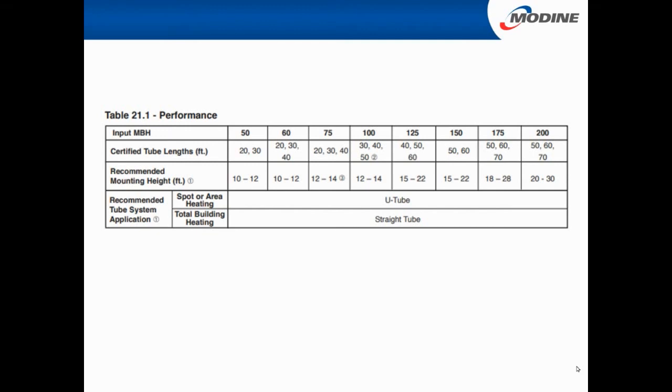We've had engineers in Denver. Well, then explain the 25 BTUs, what's the difference? It's the air shutter plate that comes with the 200, and the orifice. Those two. We've had engineers down in Denver at 5,500 feet, and we have one of these in our warehouse, and they can't get it to work there. They've done everything. They drilled holes, they restricted it. They just have issues with the 200s. So just don't sell them. It's not in the picture.